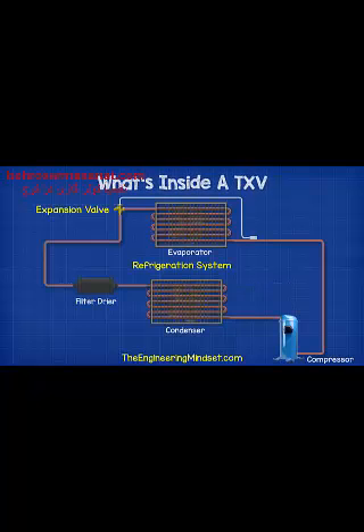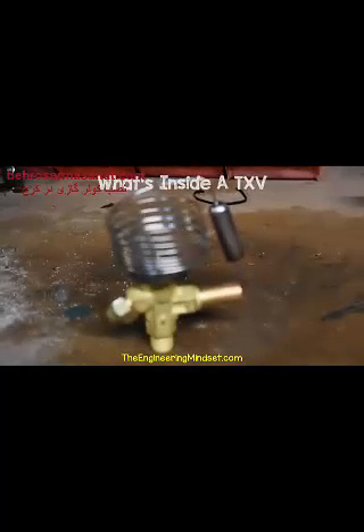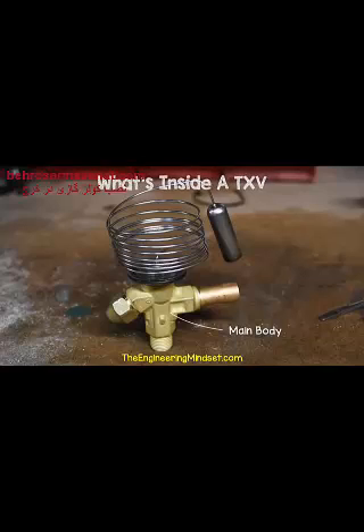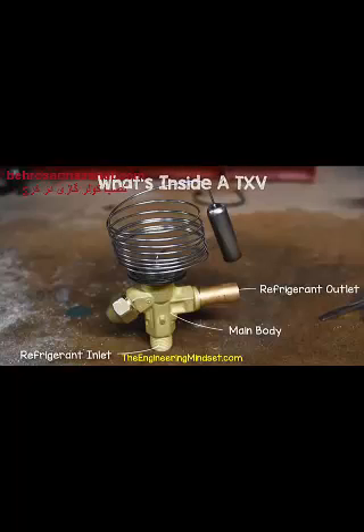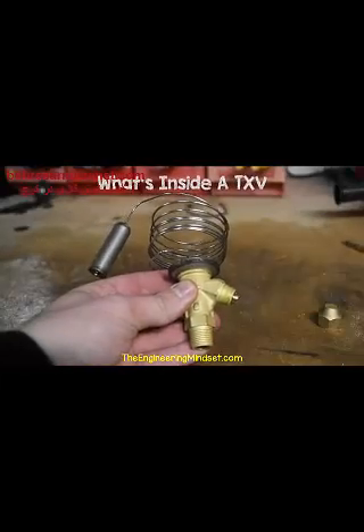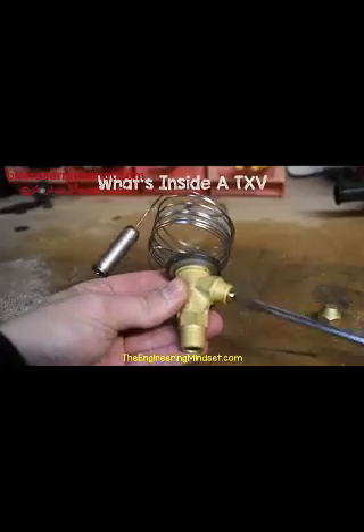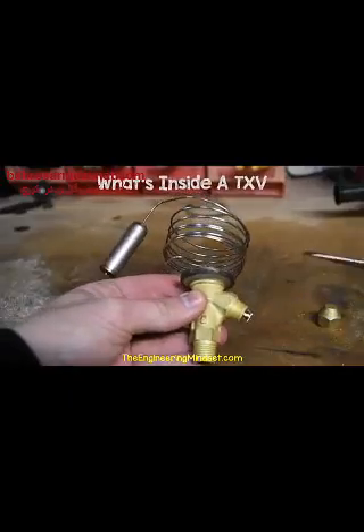Expansion valves sit between the condenser and the evaporator in a refrigeration cycle. In this model, which is a TXV, thermal expansion valve, we have the main body, which is made from brass. On the body, we have the refrigerant inlet at the bottom of the valve, then the refrigerant outlet at the side. And on the other side, we have a cap which can be removed. Under that cap is a screw which is used to manually adjust the superheat. We'll see how that works later on in this video.